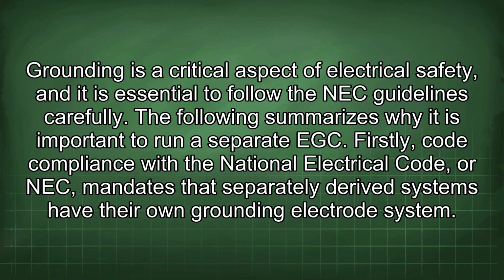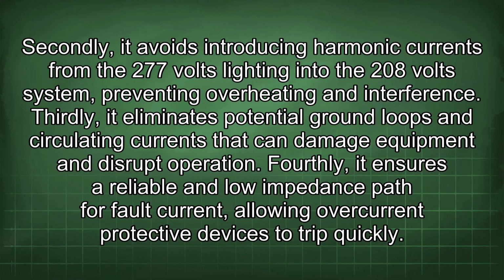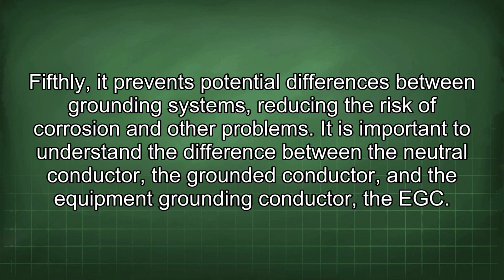The following summarizes why it is important to run a separate EGC. Firstly, code compliance: the National Electrical Code, or NEC, mandates that separately derived systems have their own grounding electrode system. Secondly, it avoids introducing harmonic currents from the 277 volts lighting into the 208 volt system, preventing overheating and interference. Thirdly, it eliminates potential ground loops and circulating currents that can damage equipment and disrupt operation. Fourthly, it ensures a reliable and low impedance path for fault current, allowing overcurrent protective devices to trip quickly. Fifthly, it prevents potential differences between grounding systems, reducing the risk of corrosion and other problems.